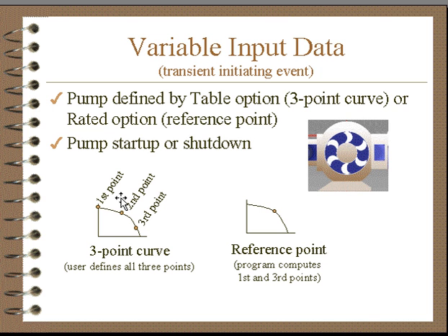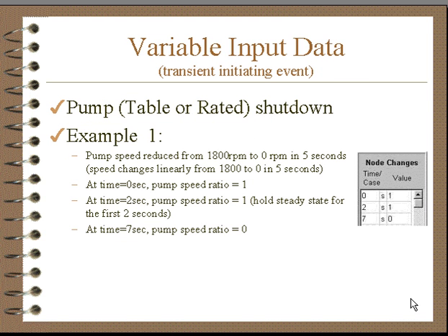For pumps defined by three-point curves or reference points, which are rated conditions which we also transform into a three-point curve, the data will be the speed and time. At this particular setup, at time zero, the speed is one, meaning it's running full speed. At time two, the speed is one, so it holds the steady state for two seconds. And at time seven, the speed is zero.